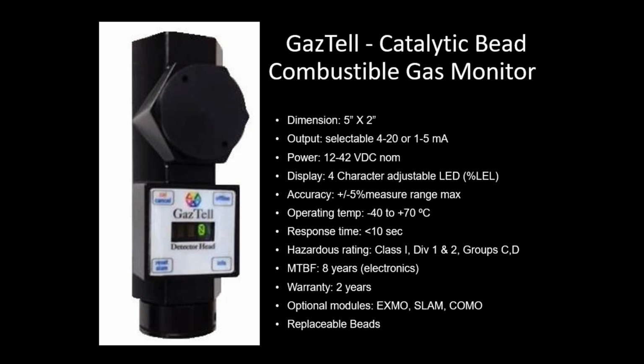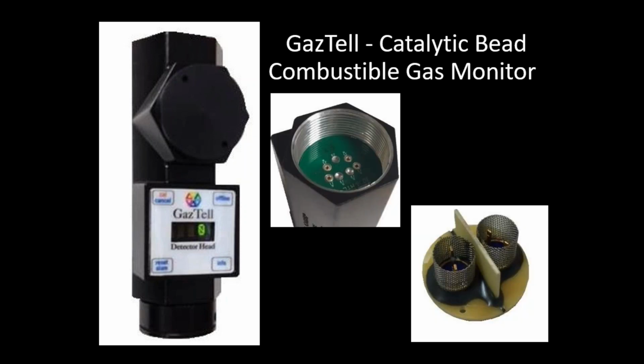The beauty of the catalytic bead GazTell is that the elements themselves are replaceable. And what we've done is we've designed something very similar to our 550 common sensor. We've designed replaceable elements, and these elements can be removed from the bottom of the sensor when you remove the flame arrestor. This allows you to buy a sensor body, a detector head, and use it for your 10 to 15 years and just replace the element at a much lower cost than replacing the whole sensor itself. Okay, and with a lot of competition, you have to replace the entire sensor for the cost of the body as well as the sensor.